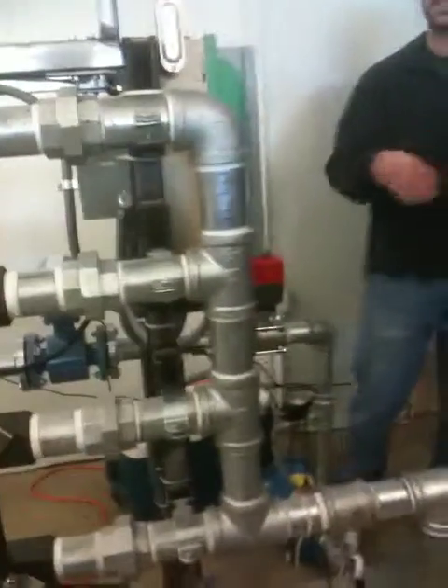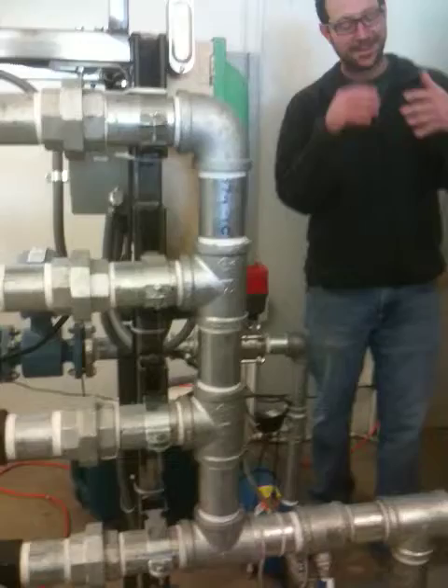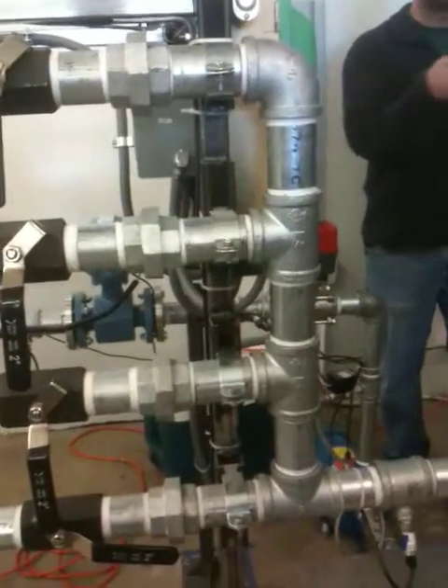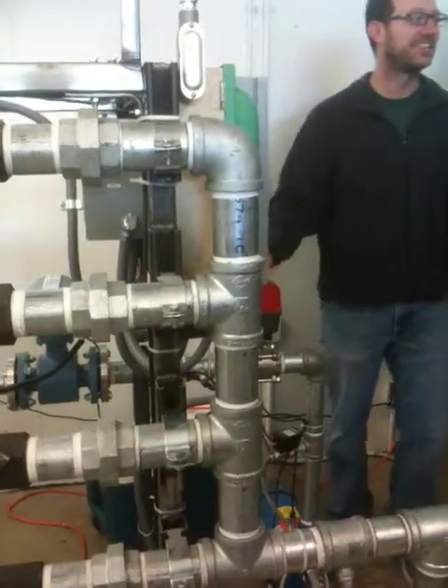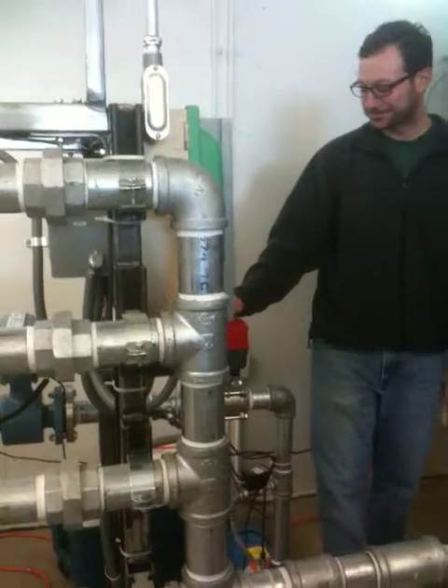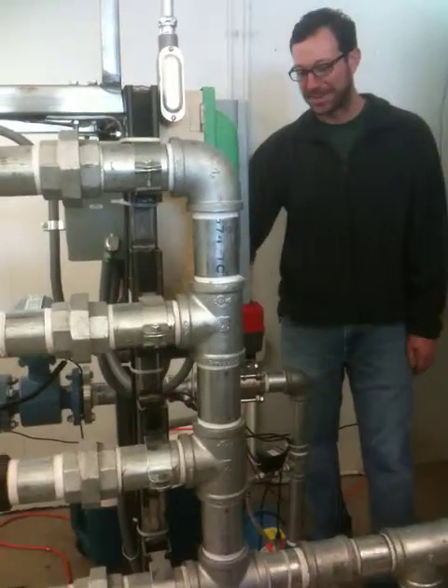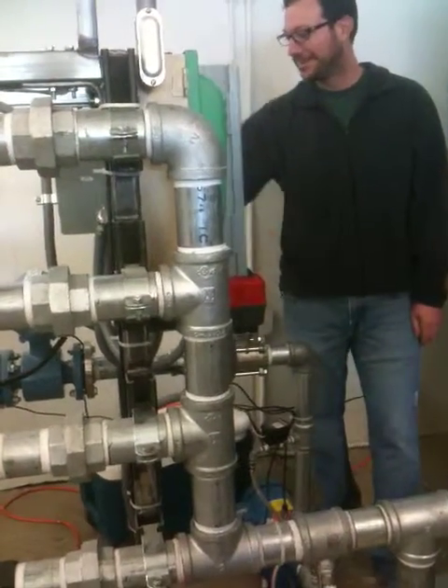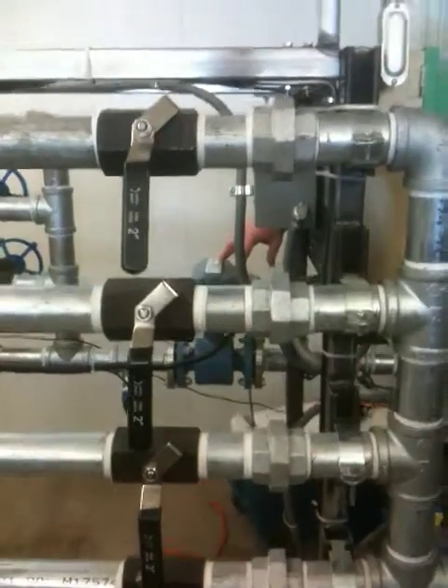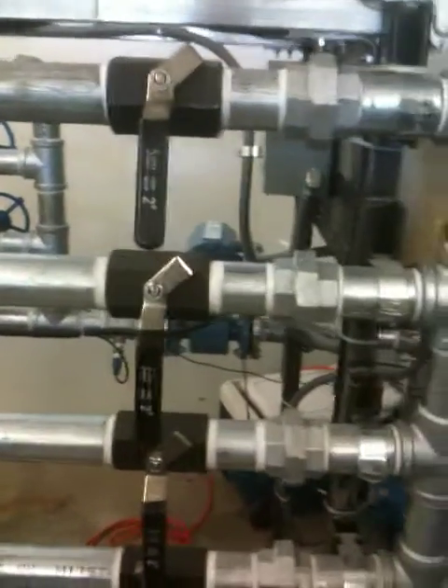I think the dead zone isn't large enough, so if you tell it like 50 gallons per minute, it goes to 52 and 47 and 52 and 47, it just keeps going back and forth. So we don't mess with that. So you can just manually open and close this valve. Magnetic flow meter, very accurate, precise way to measure flow rate.